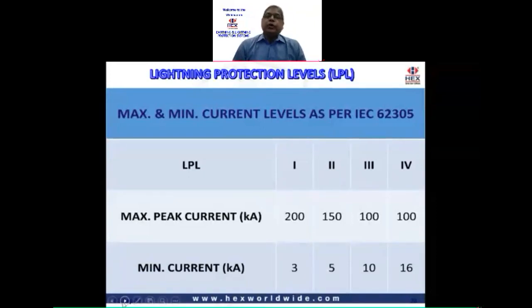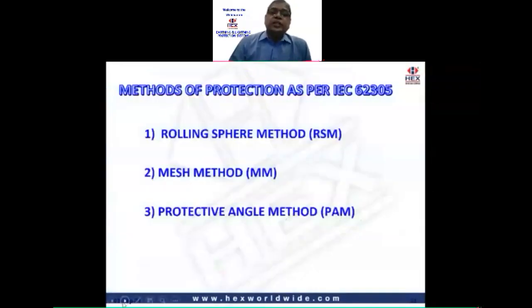Now, based on these four LPLs, or lightning protection levels, both these standards have classified the lightning protection system into four corresponding types. So each lightning protection level will have level 1 LPS, level 2 LPS, level 3 LPS, and level 4 LPS. Let us see the three methods. IEC 62305 states that we can use three methods to design the lightning protection system. That is the RSM, or rolling sphere method. The second is the mesh method. And the third is the protective angle method, or PAM as it is called. Let us see how these three methods can be used.